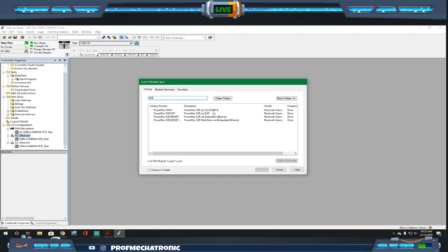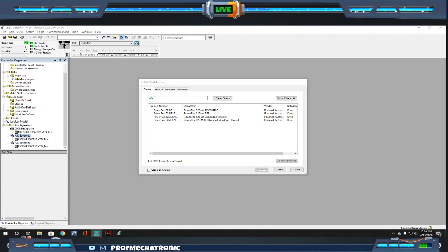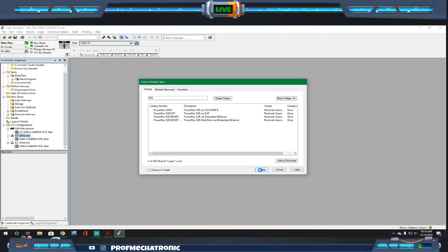So we have the 525 via a 22COM-E, which is an extra module you would install into the PowerFlex 525. You also have the PowerFlex 525 via E2P, which is another adapter. You have embedded Ethernet, which is the one we're obviously going to use, and a multi-drive via embedded Ethernet, used as the master to control multiple drives over serial communications. For us, what we really care about is the embedded Ethernet, so we're going to click on that and hit create.